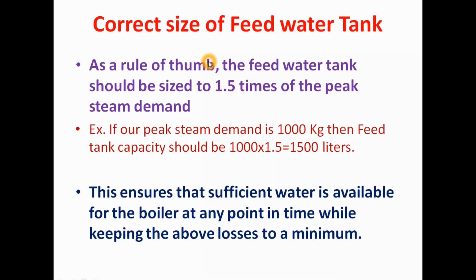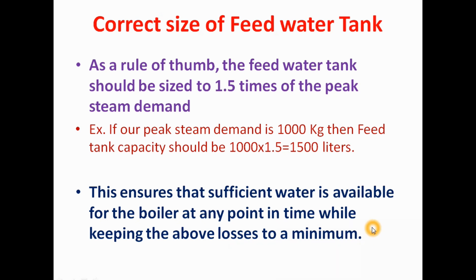Now we will see how to design the correct size of a feed water tank. As a thumb rule, the feed water tank should be 1.5 times the peak steam demand. For example, if peak steam demand is 1000 kg per hour, then the feed water tank capacity should be 1.5 × 1000 = 1500 kg. Using this thumb rule ensures sufficient water is available for the boiler at any point in time while keeping losses to a minimum.